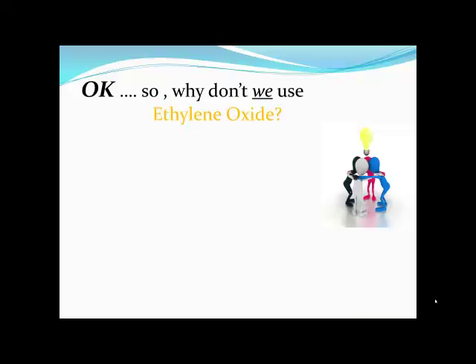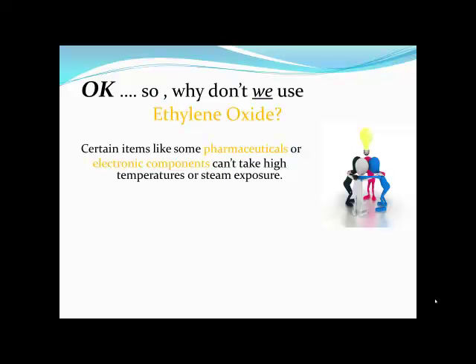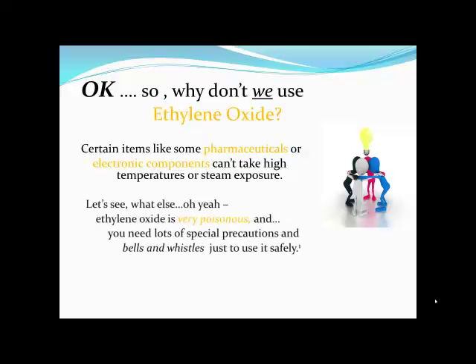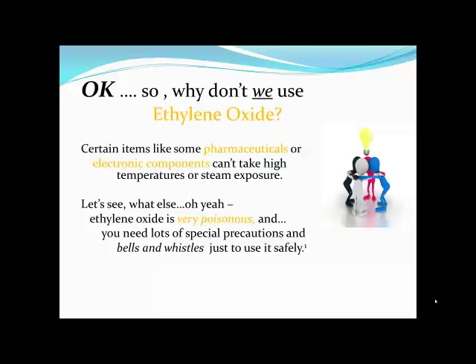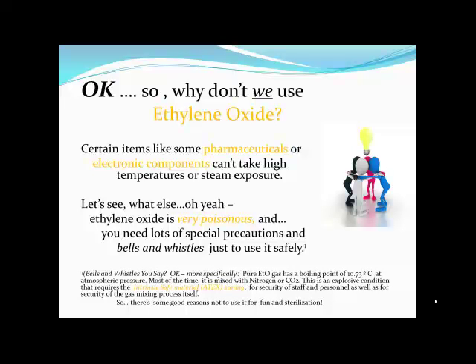So why don't we use ethylene oxide? Well, certain items like pharmaceuticals or electronic components can't take high temperatures or steam exposure. But also, ethylene oxide is very poisonous, and you need lots of special precautions just to use it safely. More specifically, ethylene oxide has a boiling point of 10.73 degrees Celsius at atmospheric pressure. Mixed with nitrogen or carbon dioxide, this is an explosive condition that requires intrinsic safe material zoning for the security of staff and personnel, as well as for the gas mixing process itself. So there are some good reasons not to use it.